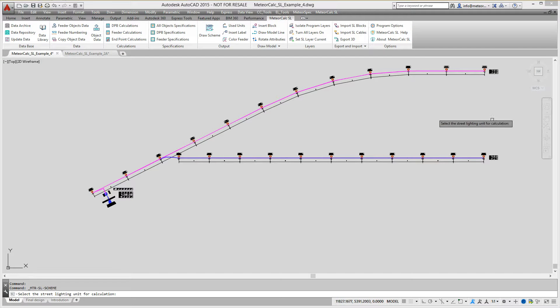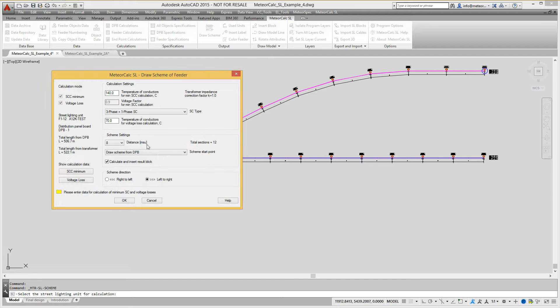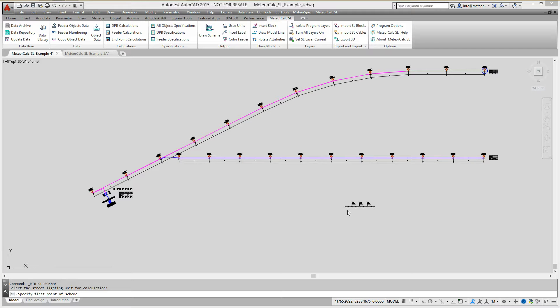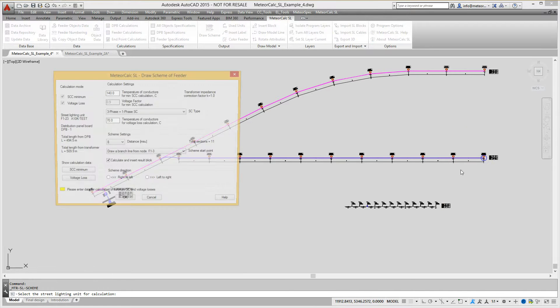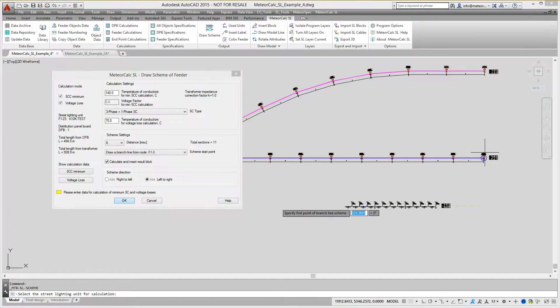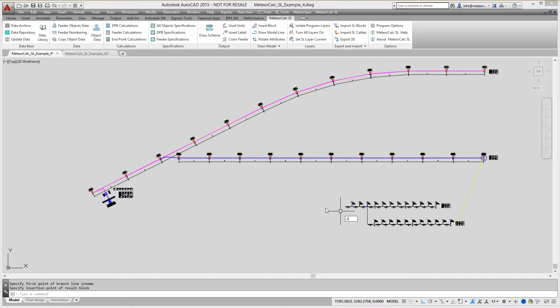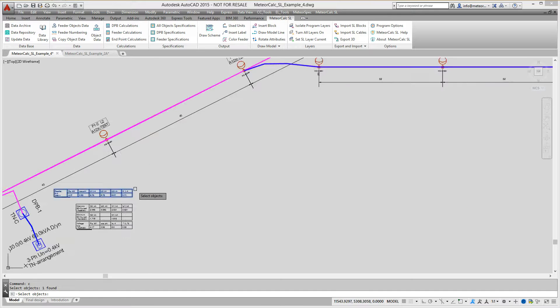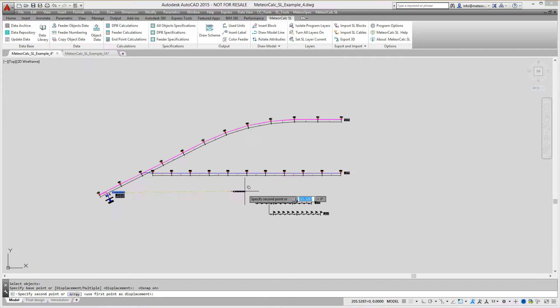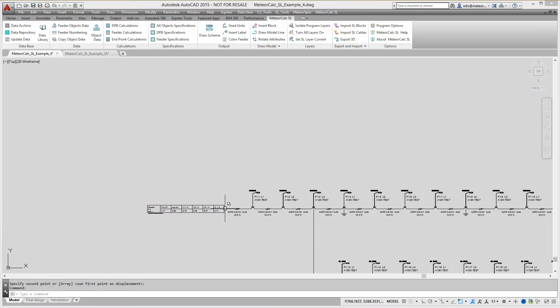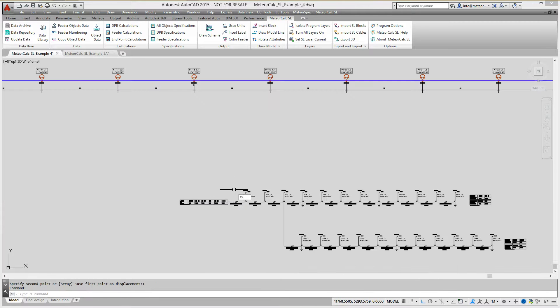Now we are ready for drawing the electrical single-line scheme of the feeder. We begin drawing a scheme with the main line. The calculations of short-circuit currents and voltage losses are performed at the selected endpoint while drawing the diagrams. We can set the direction of the scheme and other scheme parameters in the dialog window. We draw the scheme of branch lines analogically. MeteorCalc automatically determines the point of branching. The user only has to specify a point at the top or the bottom of the block for drawing branches. Fault currents computed at the endpoints and operating currents in feeders allow us to choose and check a protective device in the feeder.